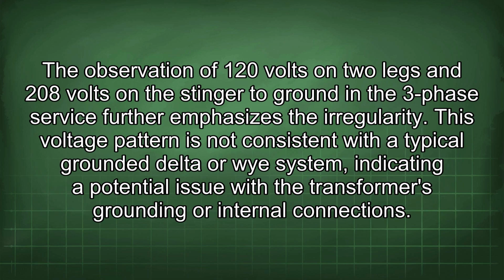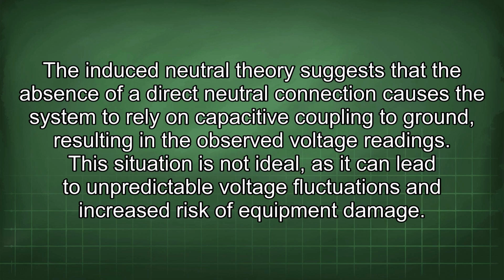The observation of 120 volts on two legs and 208 volts on the stinger to ground in the three-phase service further emphasizes the irregularity. This voltage pattern is not consistent with a typical grounded delta or Y system, indicating a potential issue with the transformer's grounding or internal connections. The induced neutral theory suggests that the absence of a direct neutral connection causes the system to rely on capacitive coupling to ground, resulting in the observed voltage readings. This situation is not ideal, as it can lead to unpredictable voltage fluctuations and increased risk of equipment damage.